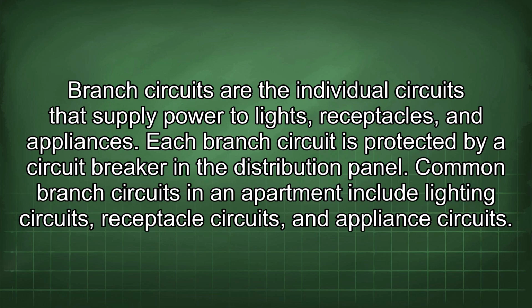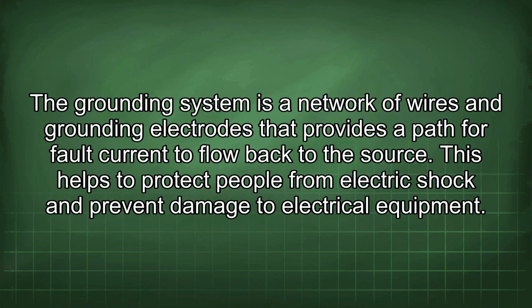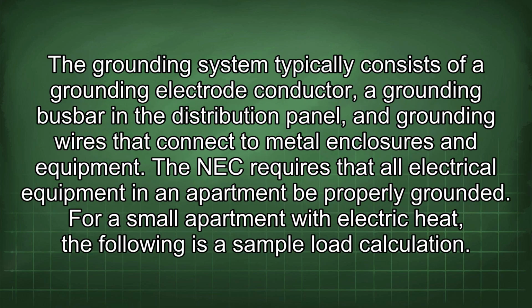Common branch circuits in an apartment include lighting circuits, receptacle circuits, and appliance circuits. The grounding system is a network of wires and grounding electrodes that provides a path for fault current to flow back to the source. This helps to protect people from electric shock and prevent damage to electrical equipment. The grounding system typically consists of a grounding electrode conductor, a grounding busbar in the distribution panel, and grounding wires that connect to metal enclosures and equipment. The NEC requires that all electrical equipment in an apartment be properly grounded.